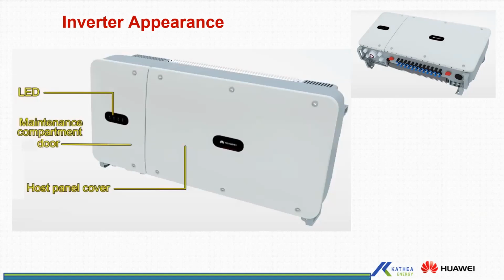Only HUAWEI technicians or engineers can open that panel. So whenever you have these inverters, do not open the host panel. Opening it will void your warranty. There is a seal on it, so if you tamper and open the unit, it won't be covered under warranty. The compartment for the installer is the one which you call the maintenance compartment. In this case, it is the smaller one on the left side.